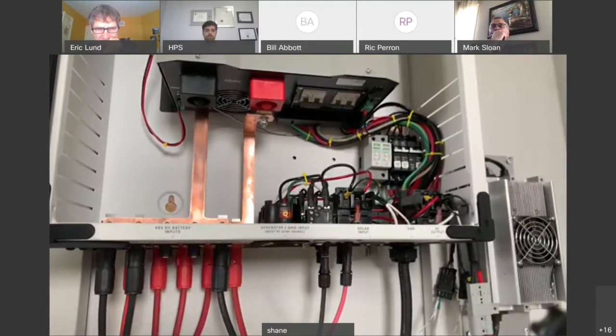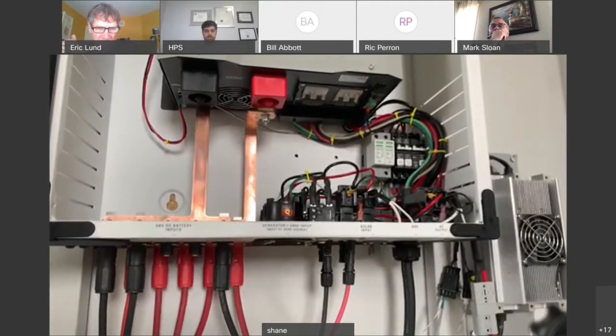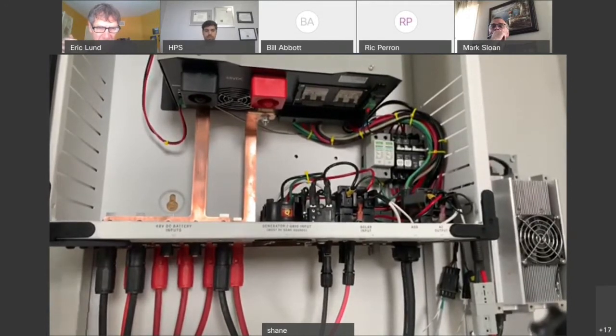So if you do have to have a larger generator, for example, I have a 20 kilowatt propane Cummins generator tied into one of these, and I have 2 whips coming off of a junction box. So I'm going into both inputs so that I could still run the charger at full capacity and run the camp at full capacity while pulling 14 kilowatts out of the generator. This way nothing gets overloaded.